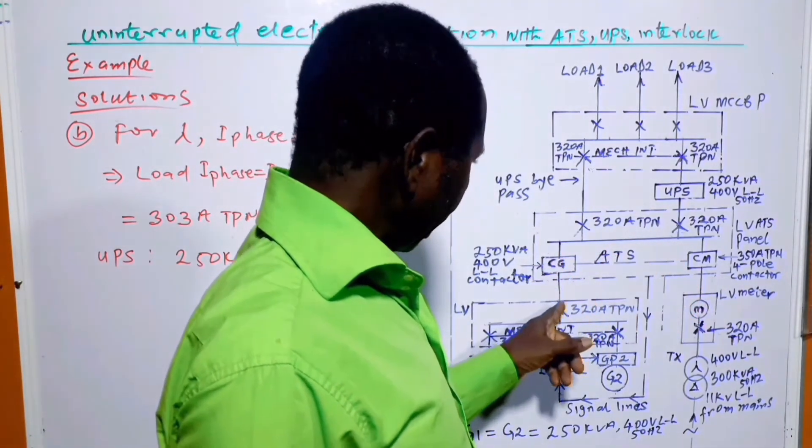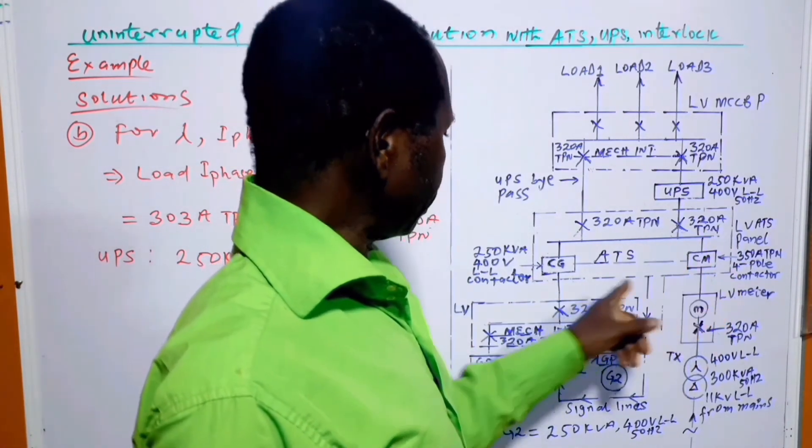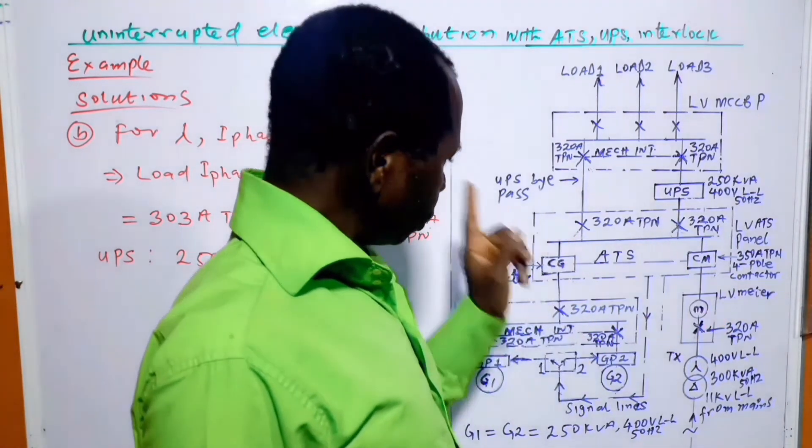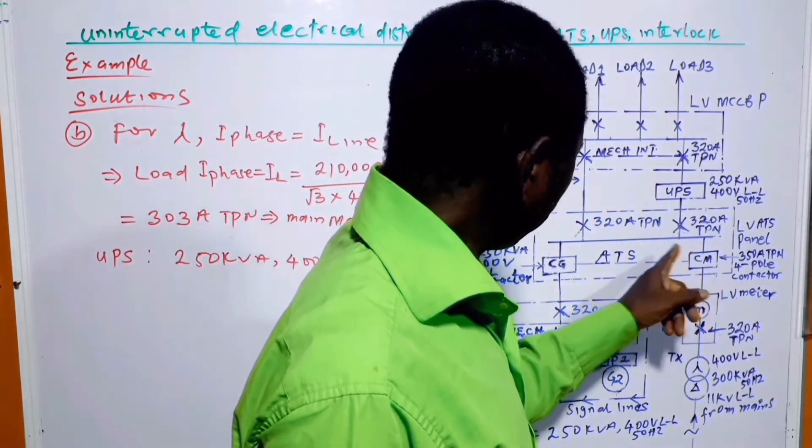It is this link that is called the ATS automatic transfer switch. When this contactor is energized, this one is de-energized. When this one is energized, this one is de-energized. The two of them cannot be energized at the same time.